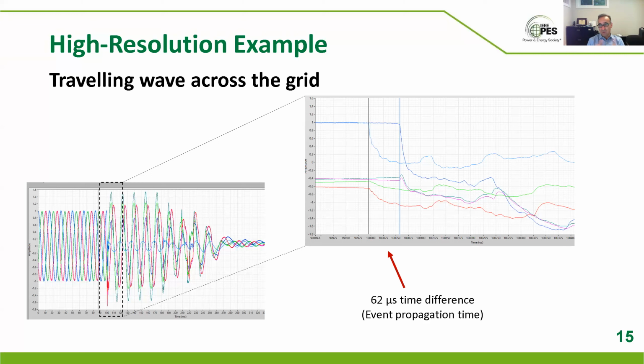That travels in both directions along the line, or all directions, I should say. And basically, the travel speed depends on the dielectric constant of the medium. For overhead transmission lines, that's mostly air, so this wave travels very close to the speed of light. The scientists say 3 times 10 to the power 8 meters per second. The engineer in me says that's 300 meters per microsecond. So that wave is traveling, it's the same thing, just a different way of expressing it.